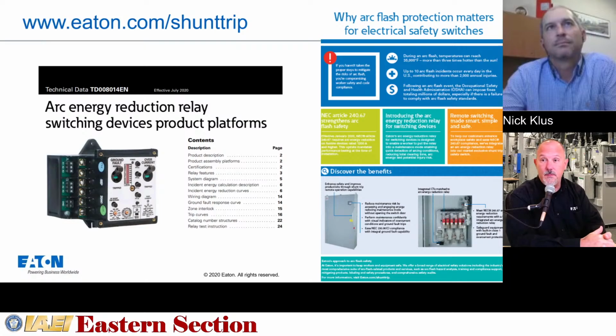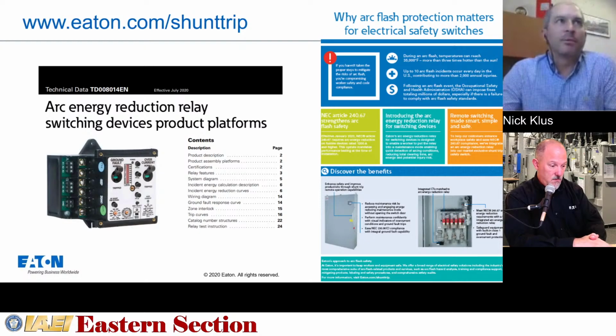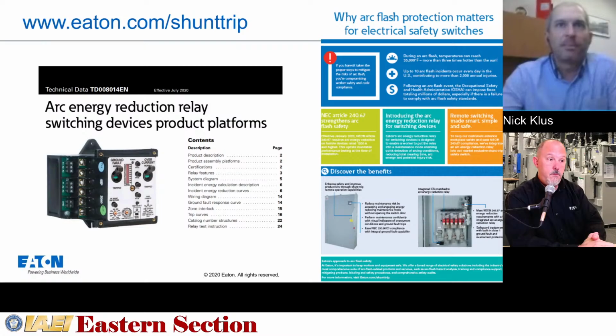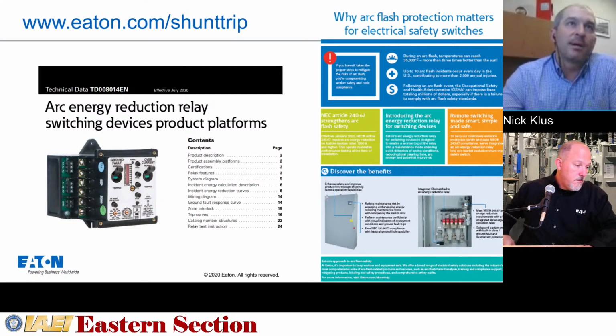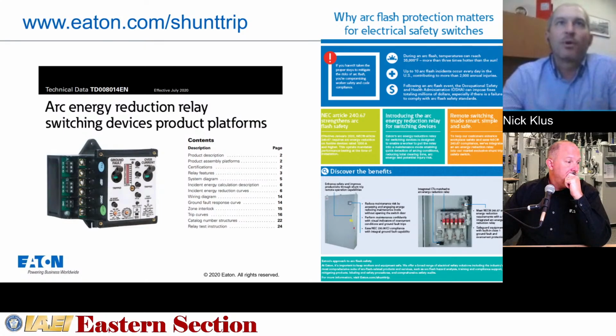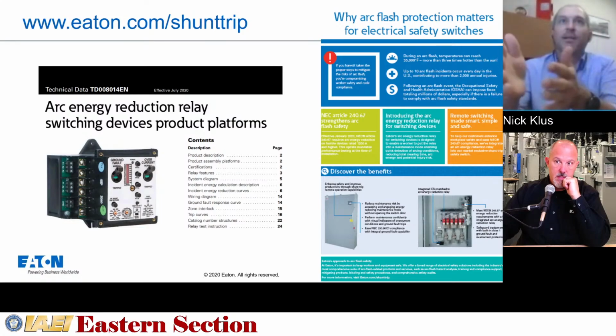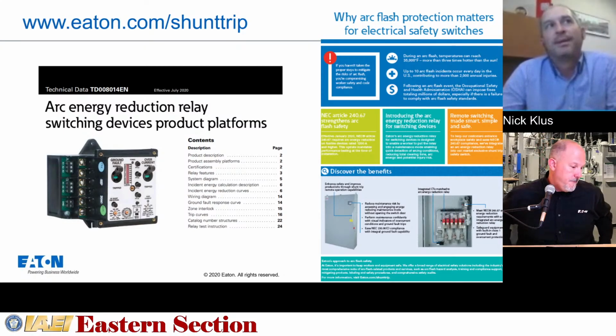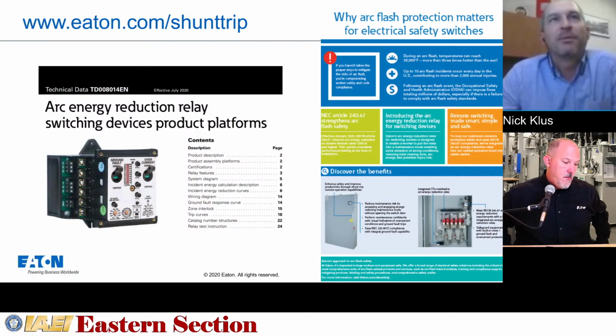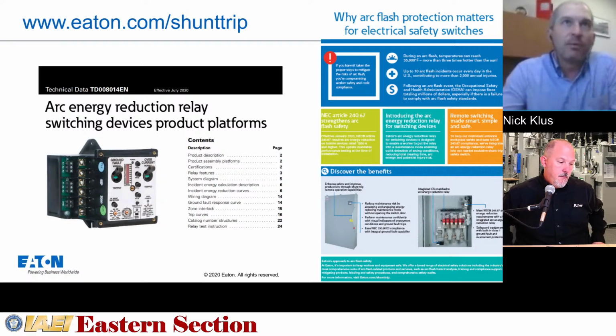I don't know, Nick, if that makes sense. Anything to add on that one? Yeah, I think you're right, in that different installations have different things that go into that, and a study in each case can tell you what those PPE levels are. What I will say though is whether it's this device or the ARMS circuit breaker, which by the way we do have a standalone enclosed version of that breaker that Manny was talking about, if you don't need an entire switchboard, we have seen instances where people have done those studies and they say, my calculations are showing that I need to find some way of having arc energy reduction at, let's say, this main leg only motor control center. These are two really good products where you could, and I don't want to sound like I'm a contractor that's done this work before, reasonably easily put this in front of, say, a main leg only MCC or some piece of equipment where you need some energy reduction to bring the PPE more in line with where you'd like it to be than where your current system is.